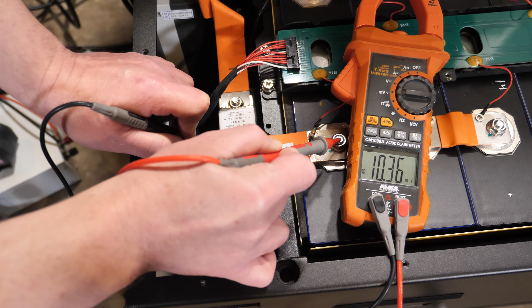The fuse by itself is showing 83.7 millivolts, and from this bus bar to the circuit breaker is 15.5. If you add it all together, it's around 109.6 millivolts. What do you say we raise it up just a tad?